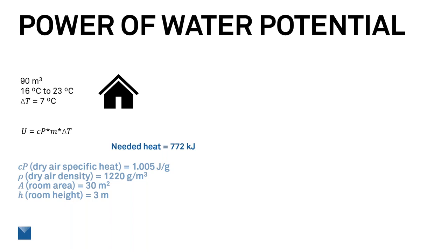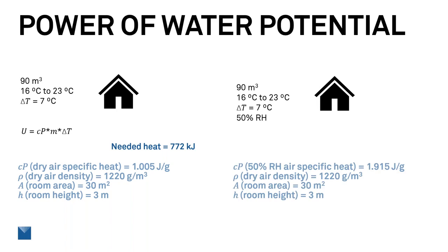Okay, so let's say we now have the same room, but it's at 50% relative humidity, and we still want to achieve that same 7-degree rise in temperature, from 16 to 23 degrees Celsius, a more comfortable temperature. At 50% relative humidity, we see a change in these variables, specifically the specific heat of air. And that one change in variable results in us now having to add 1,472 kilojoules of heat—almost double the amount of heat needed to raise the room the same temperature.